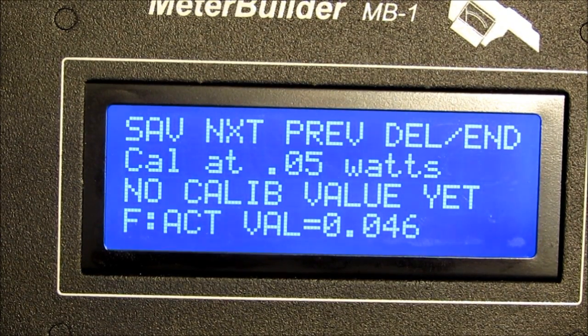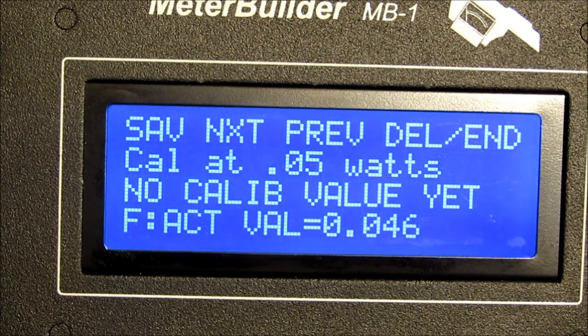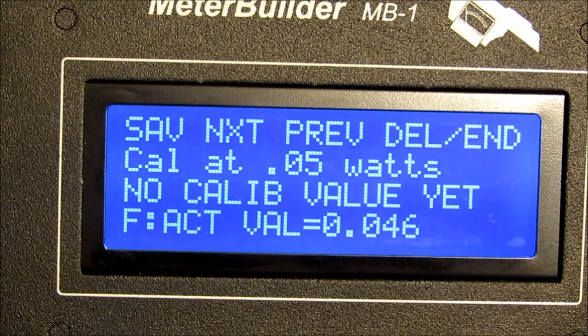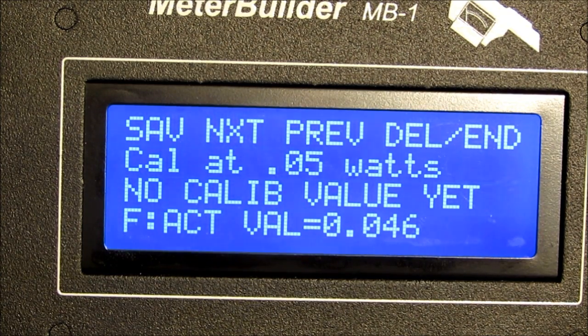We're ready to start calibration. You'll see that the software offers any of the 60 calibration points that MB-1 is capable of working at, or all points in the set determined by the full scale value that we specified, 500 watts. Now, the meter can be calibrated up to 30,000 watts, but once you tell it 500 watts is the full scale value you're calibrating it at, it'll stop offering you calibration points at 500 watts.